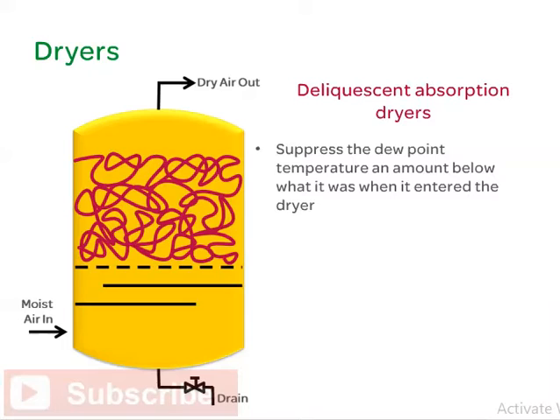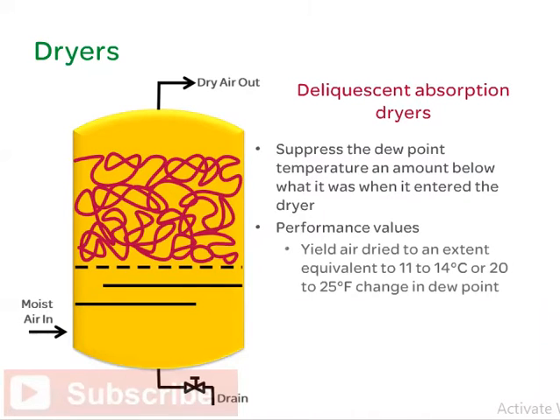Deliquescent absorption dryers are rare but can be found in certain locations. They use a medium to absorb the moisture. Over time, the medium changes from a solid to a liquid which is drained away and eventually has to be replaced. The medium may be sodium, potassium, or calcium salts or based on urea. The liquid must be properly disposed of according to environmental regulations. These dryers suppress the dew point temperature an amount below what it was when it entered the dryer. Performance values yield air dried to an extent equivalent to 11 to 14 degrees Celsius, or 20 to 25 degrees Fahrenheit, change in dew point.